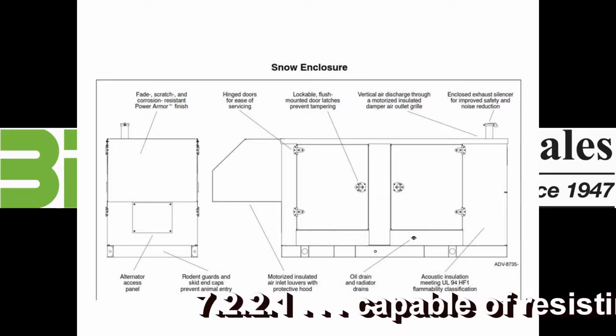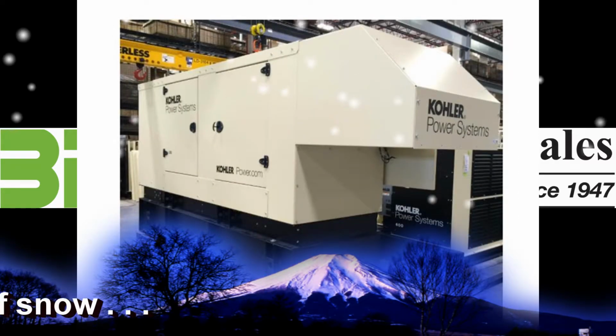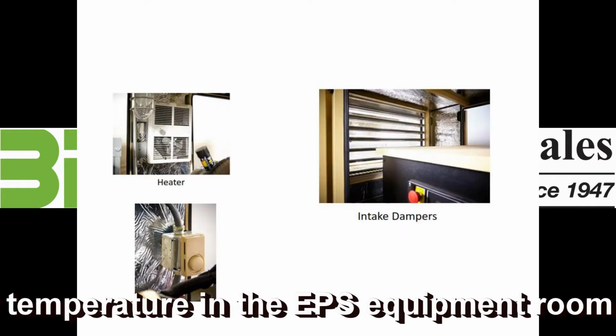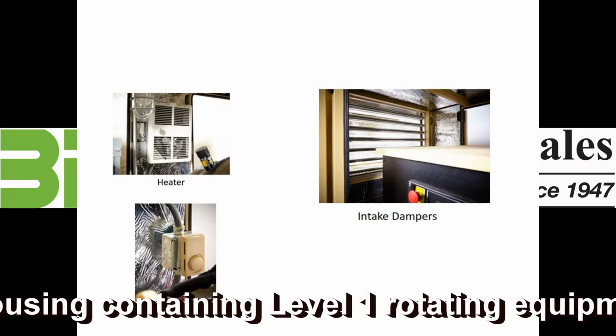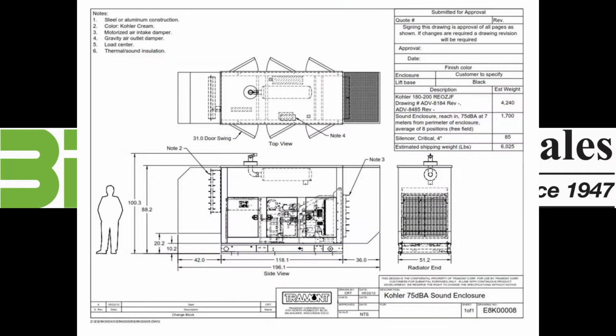For outdoor generators, there could be the need to design for winter environments. A snow enclosure to keep snow from being brought into the generator set while running. Part of that is motorized dampers for the exhaust and the intake sides, as well as heaters. This package is designed to maintain 40 degrees Fahrenheit inside the enclosure.